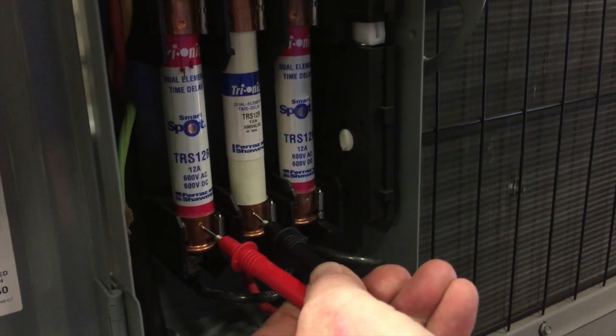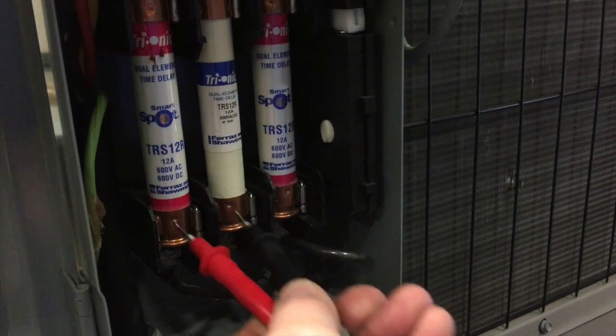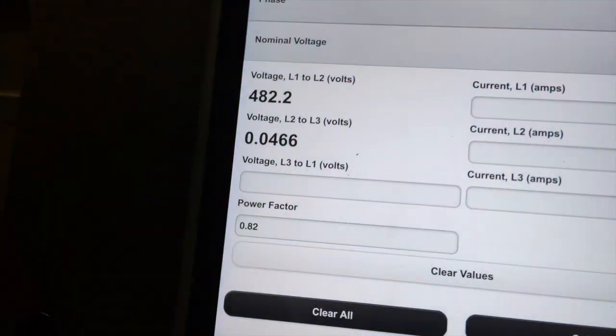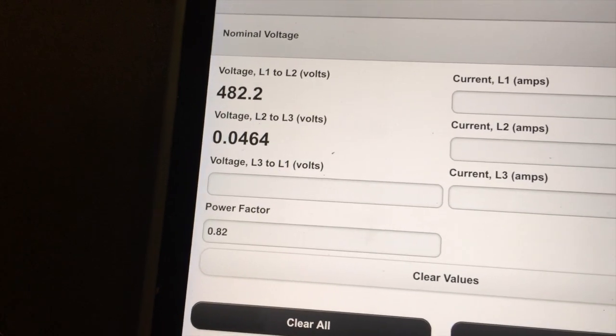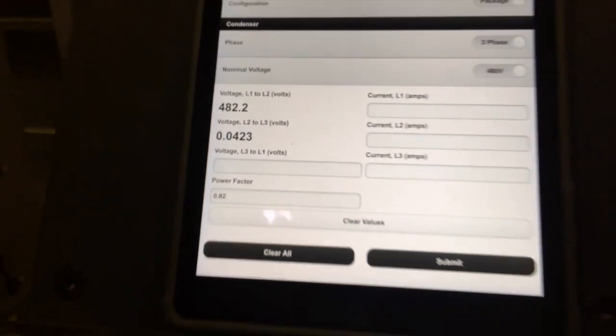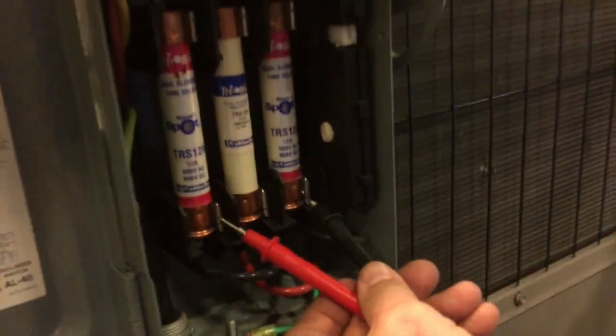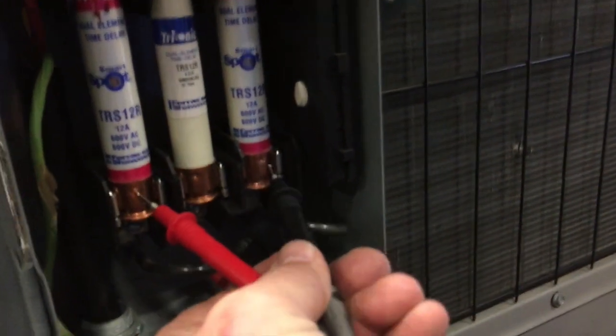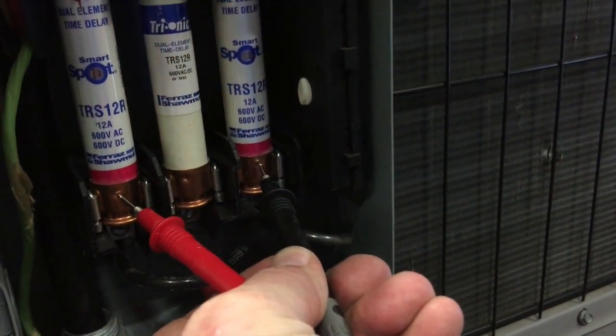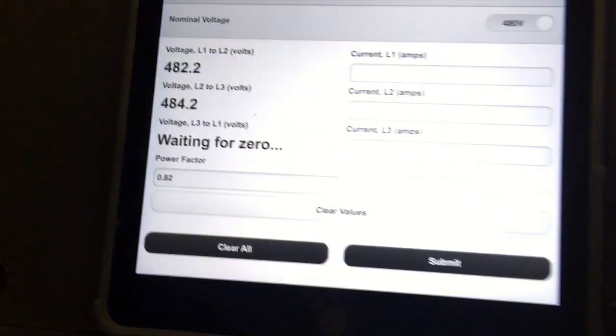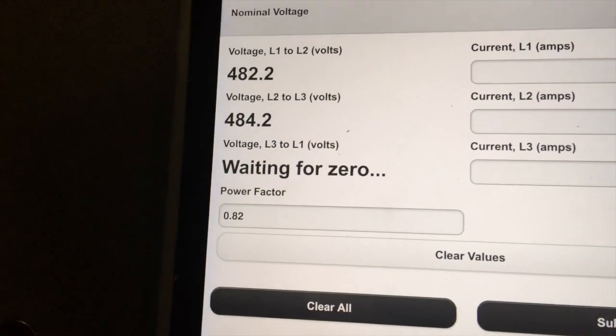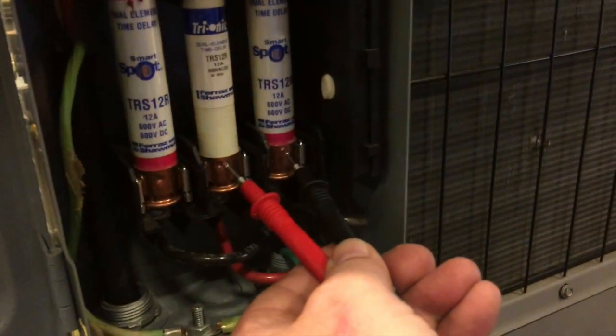And I assume you just heard the tone come in. So I'm going to go ahead and remove that for a minute, and you'll see that it recorded our first voltage reading. What it's doing is every time that you make a voltage reading, it's waiting for the meter to go back to 0 before we get the next one. So now I'm going to go L1 to L3. And if you look at the iPad, it's waiting again for the 0. So until I disconnect it, it won't go to the next reading. And now I'm going to go L2 to L3.